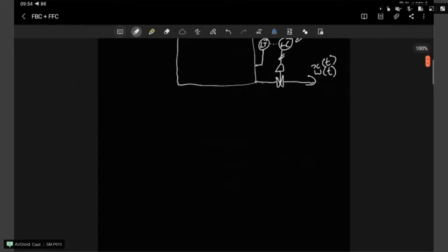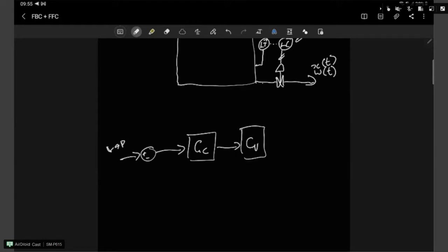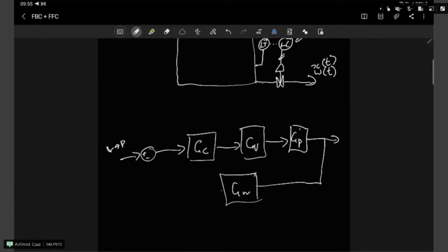When we look at the block diagram for that, it looks like this. So we have our level set point that goes into our comparator. I'm doing this in transfer function symbol, so you'll get used to this later on. Our valve. So this is where the feedback part comes in. We measure our output, which is our level. That goes through the measuring element, the sensor, and that sensor provides a signal in form of a milliamp signal to our comparator.